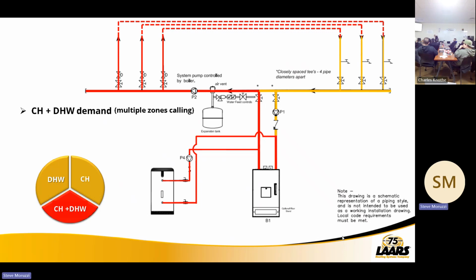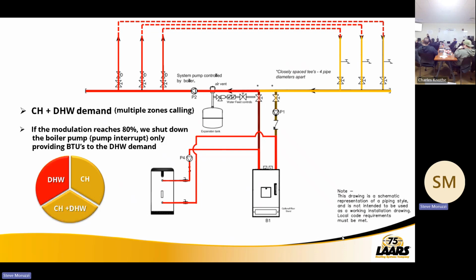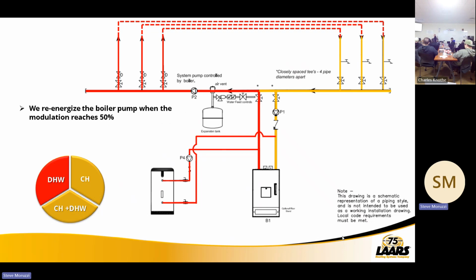Everything's been, this example is in demand. That modulation gets to 80%. We will shut off the P1 pump only. We'll allow the P2 system pump to operate, still flowing some water, and allowing the boiler now only to energize the indirect tank. As that modulates down to 50%, we will reintroduce that P1 pump, providing it again.